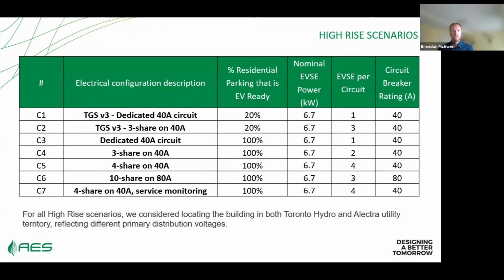Lastly, 4 share on 40 amp with service monitoring. These last three, C5 through C7, would meet the proposed performance requirements that our modeling adopted. C4 would meet those previous performance requirements that were in the Toronto Green Standard. All of these have the same circuit breaker amperage, except of course the 80 amp one, which would have an 80 amp circuit breaker, and all the charging stations would be capable of delivering 6.7 kilowatts.